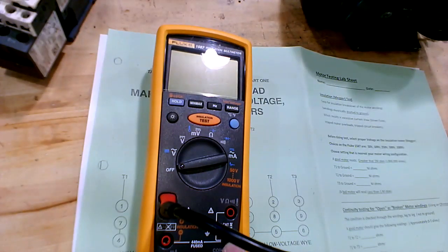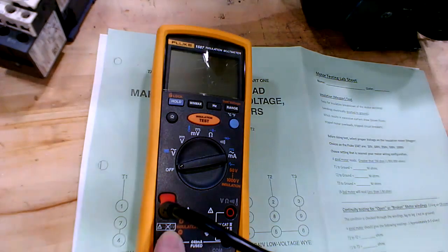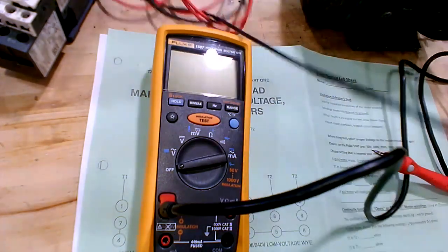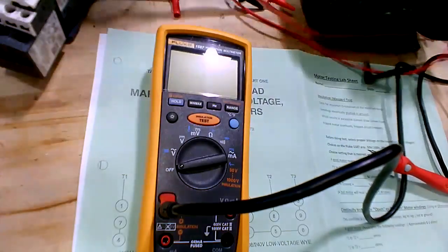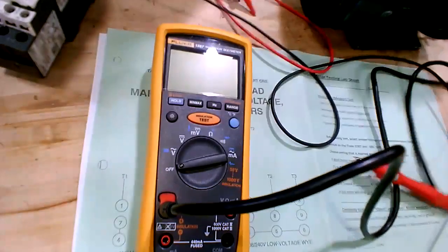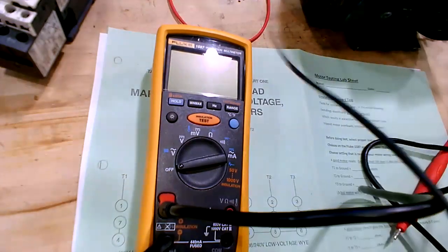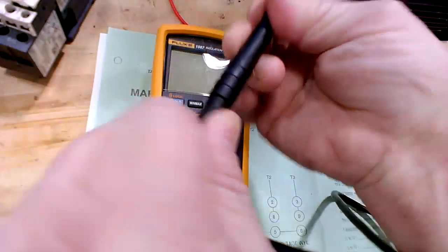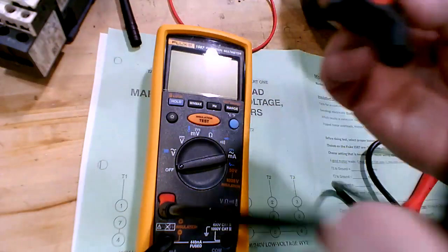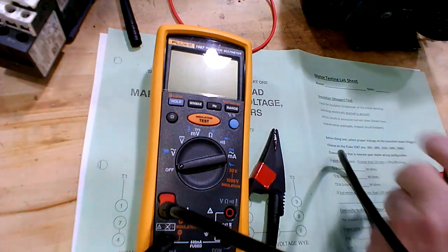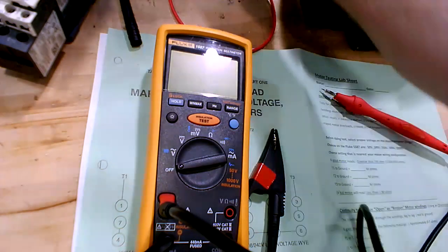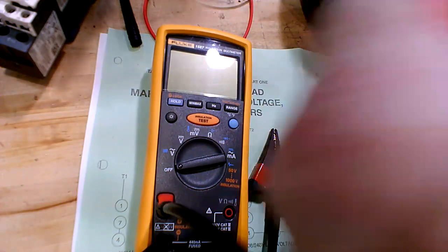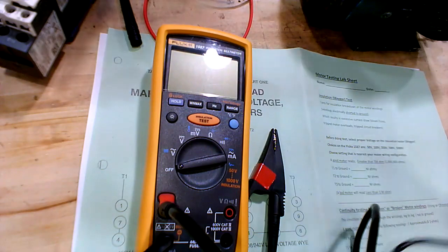And then you have to put a common, not over here, but over here for minus on insulation, in the orange. You see the orange right in there. So we take our regular plug that would normally go on the right side, and we move it over to here. So it's going to work in the orange area for doing insulation testing. And we're going to pull these off here and use the clips. That's convenient there, a test lead set. That's the banana plug connection. We can put a clip on there. It's a spring loaded connection there, so it grabs nice like that.